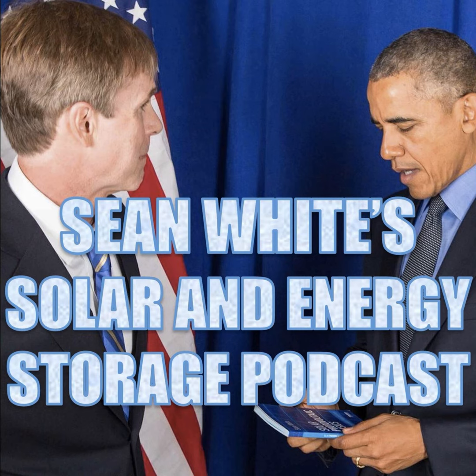Everything we say here is going to apply to anything backfeeding the grid, or will apply to a microgrid too. That's an AC microgrid because DC microgrids are in Article 712. Someday they might combine Article 705 and 712 for microgrids because there's more similarities than differences when you're microgridding stuff. What we're going to talk about here is things like anti-islanding, the MIDs, that's the Microgrid Interconnect Devices, IEEE, the Microgrid System definition, 705.11, supply-side connections, some people call that a line-side tap, and 705.12 load-side connections.